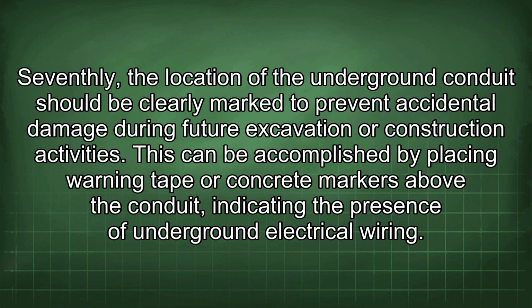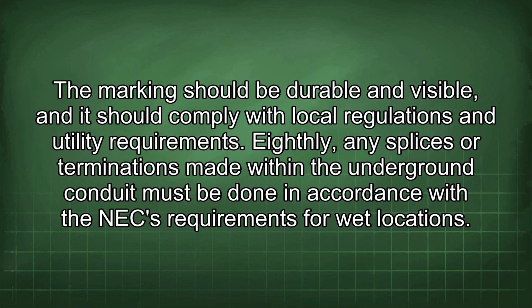Seventhly, the location of the underground conduit should be clearly marked to prevent accidental damage during future excavation or construction activities. This can be accomplished by placing warning tape or concrete markers above the conduit, indicating the presence of underground electrical wiring. The marking should be durable and visible, and it should comply with local regulations and utility requirements.